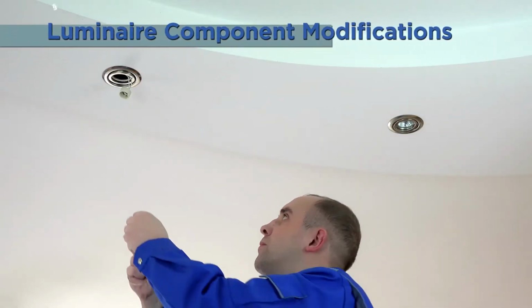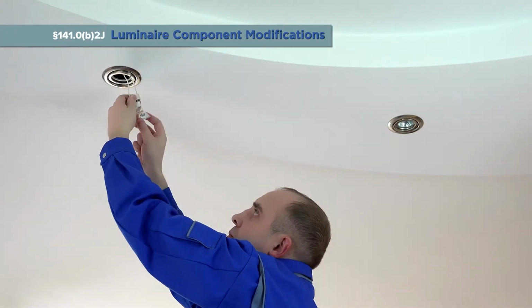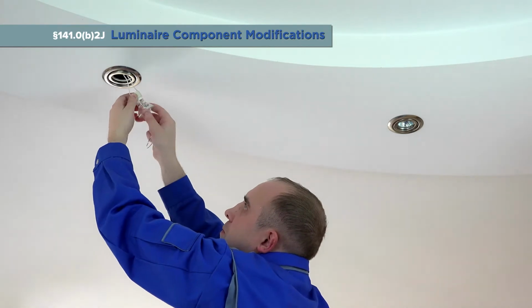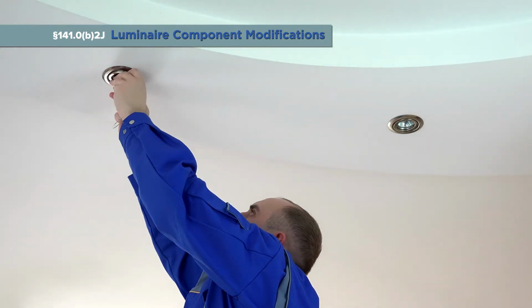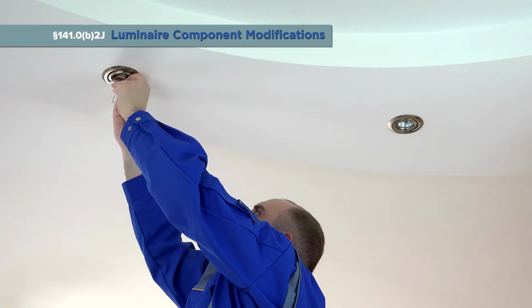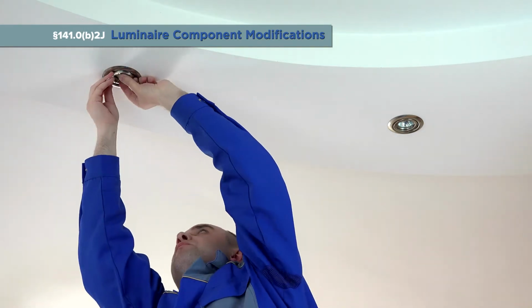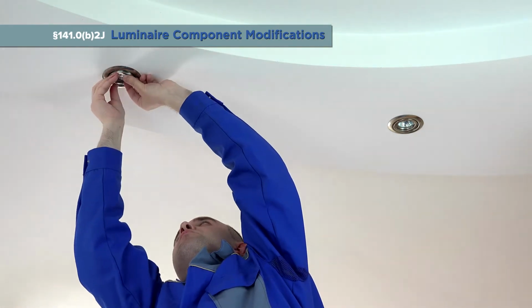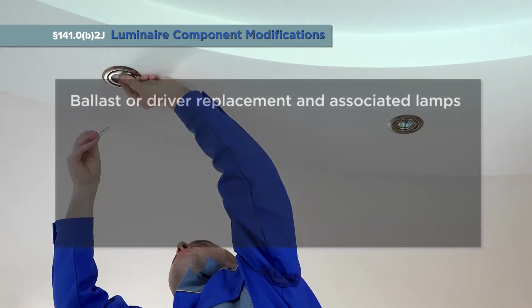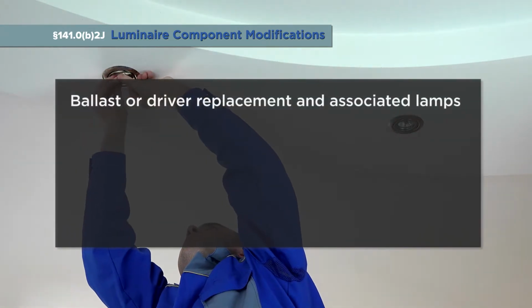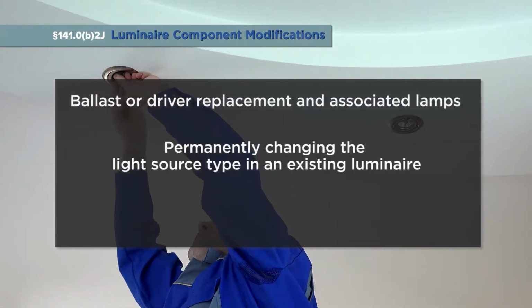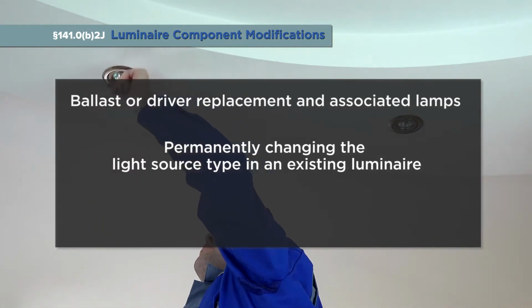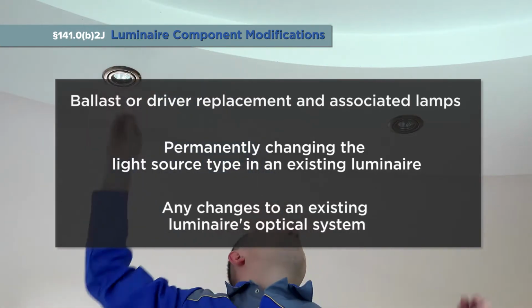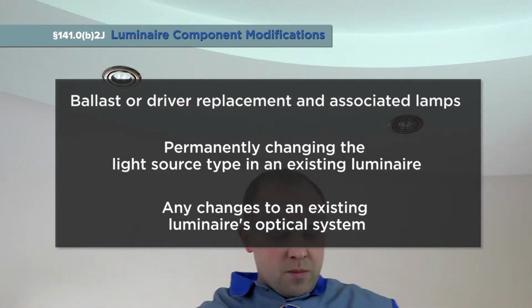The next type of indoor lighting alteration project is a luminaire component modification. These are listed under Section 141.0B2J. The scope of work under luminaire component modifications includes ballast or driver replacement and associated lamps, permanently changing the light source type in an existing luminaire, and any changes to an existing luminaire's optical system.